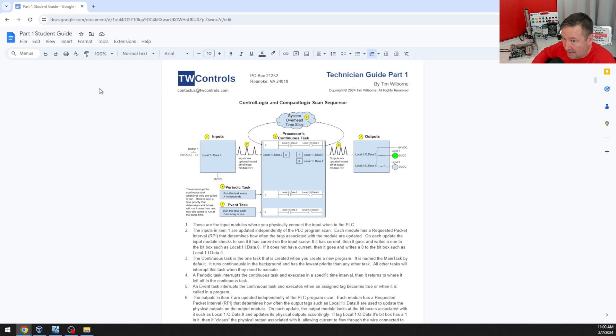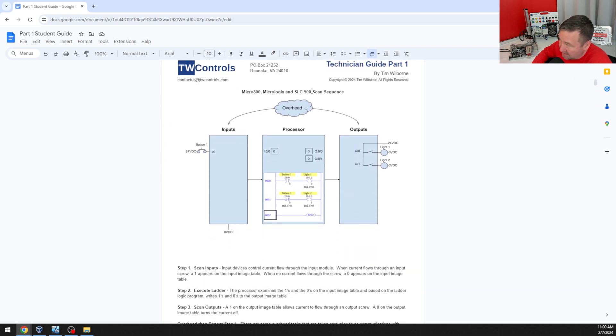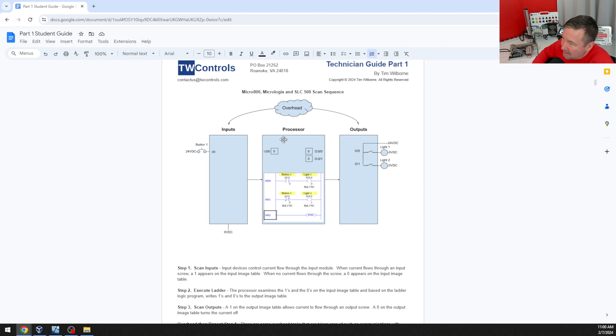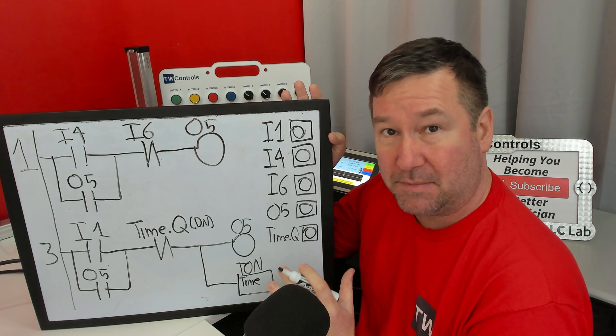There are two types of scan cycles to understand depending on which PLC you're using. We have the ControlLogix/CompactLogix scan sequence - I have a video that goes into the details of how this exact exercise works with it, just check out our lesson section. And then we have the Micro 800, MicroLogix, and SLC scan sequence, which I usually call the traditional scan cycle. In these cases, a PLC will read the value of its physical inputs and update the boxes that we go and look for ones and zeros in. Then it runs its program - starting at rung zero with the left instruction and working its way through each instruction to the right, then going to rung one, all the way through to the end of the program. Then it updates its physical outputs based on what are in those boxes.